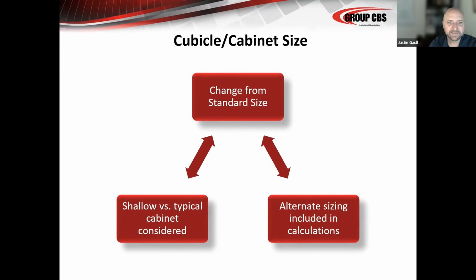Sure, yeah. This question is regarding IEEE 1584 2018 enclosure size. What size of enclosure is modeled while the draw out type circuit breaker is installed? The breaker takes up most of the box space with little room around each side. They still use the total volume of the cell, because they can't predict if an arc flash happens while a breaker is being racked in or out, where that breaker is in the process. So you can't say the breaker is always 75% in the cell versus 25% inside the cell versus 100% inside the cell. So they go with the volume of the cell. They had to pick a path, and that's the path they chose.